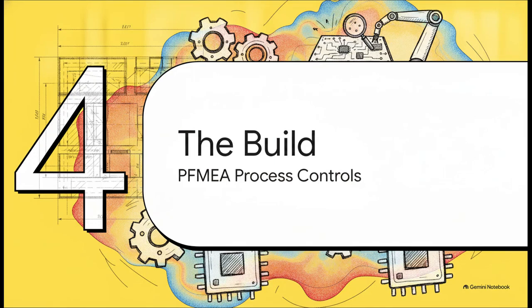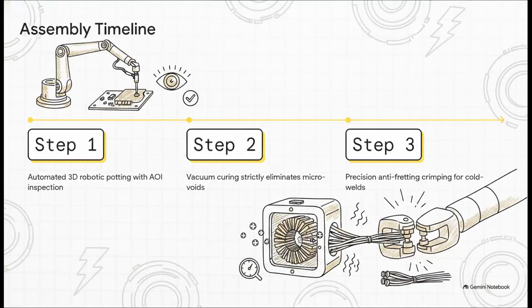Up next is Section 4, the build, focusing on PFMEA process controls. Flawless blueprints demand flawless execution, right? This means absolute total automation on the assembly line to eliminate human error. Manual assembly of temperature sensors is completely banned on these lines. Instead, 3D automated robotic dispensers apply highly thermally conductive adhesives, immediately followed by automatic optical inspection to guarantee 100% coverage with zero air pockets. Then, they lock in incredibly strict pressure and temperature curves during the vacuum pressure impregnation, or VPI, curing process. This ensures the insulation resin has absolutely zero microscopic air bubbles, completely eliminating the risk of high voltage breakdowns when temperatures spike.